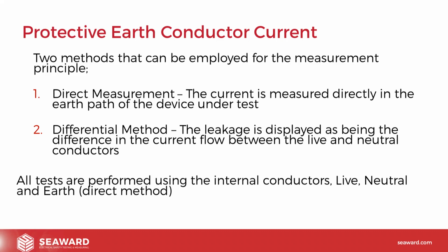All the current flowing up through the live is flowing through the device, and all of that current is flowing back via the neutral. So it flows up through the live, through the device, back down through the neutral, and there's no difference in the current. Where we do have leakage, then we may have a difference in the currents flowing in the two conductors, and that is essentially how the differential method works. It just simply understands the difference between the current flowing in the live and the neutral conductors.